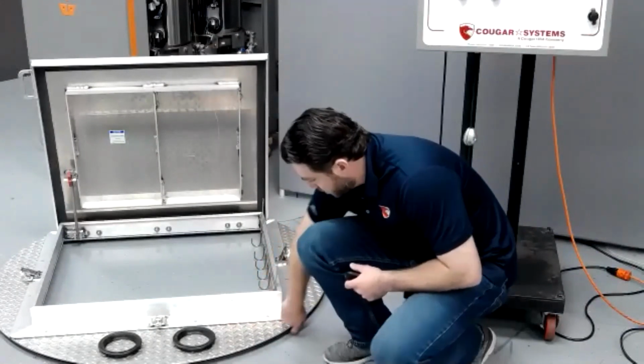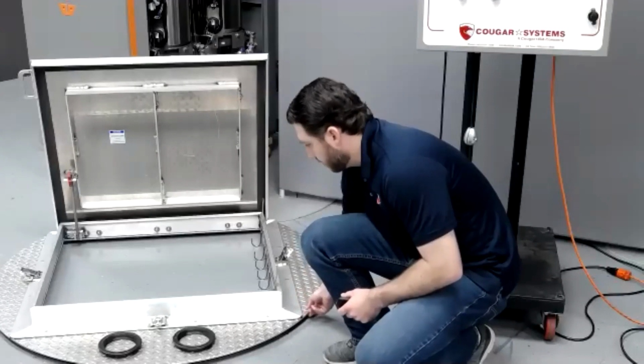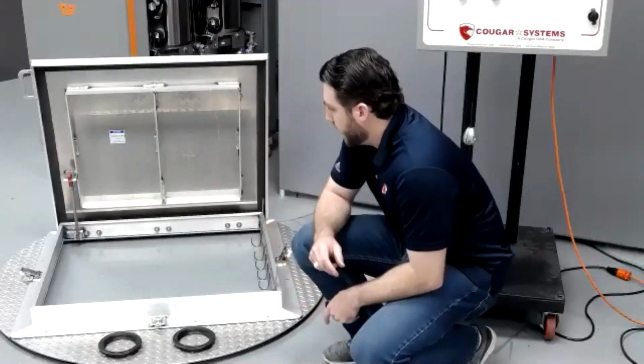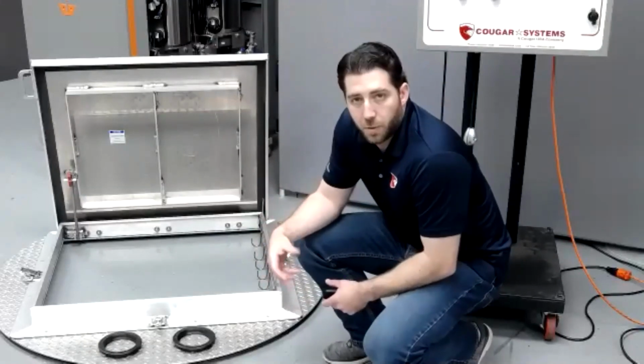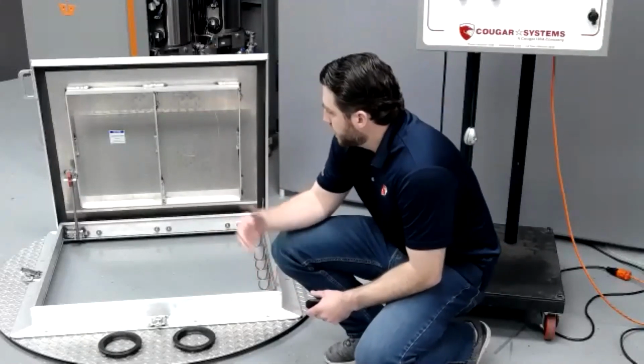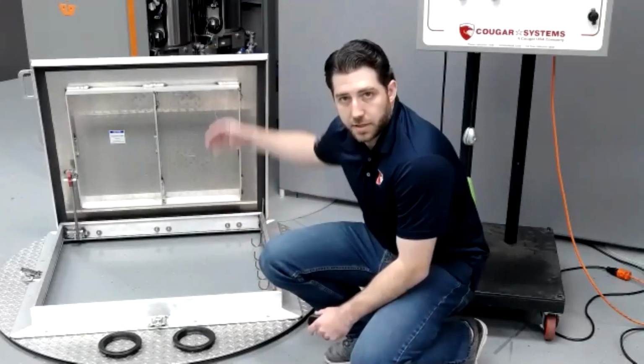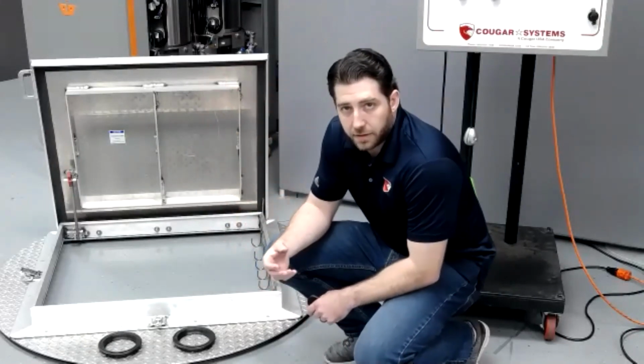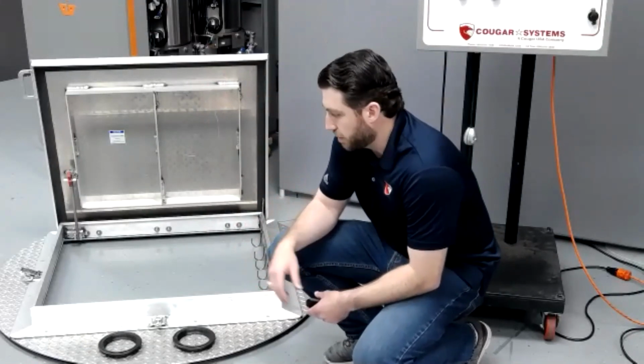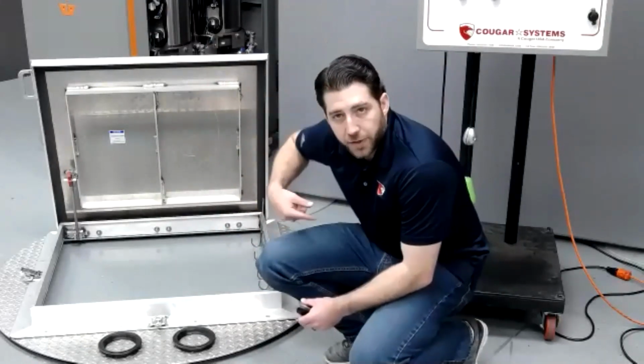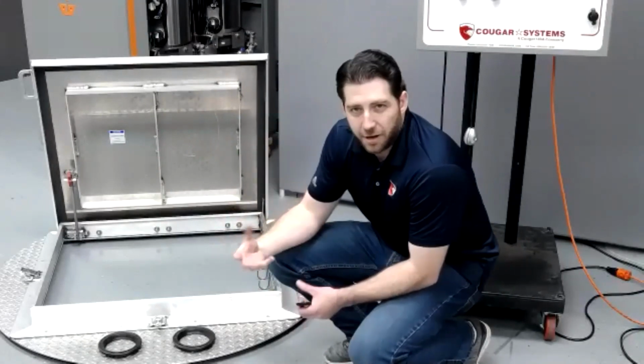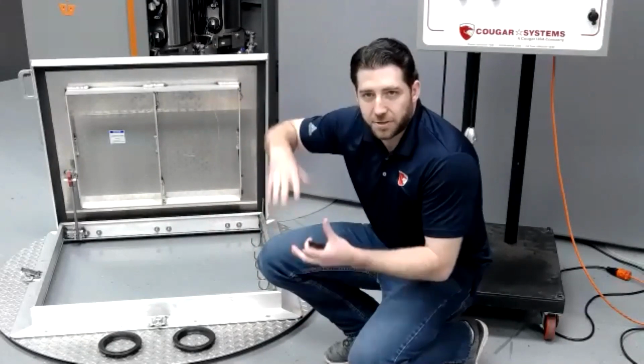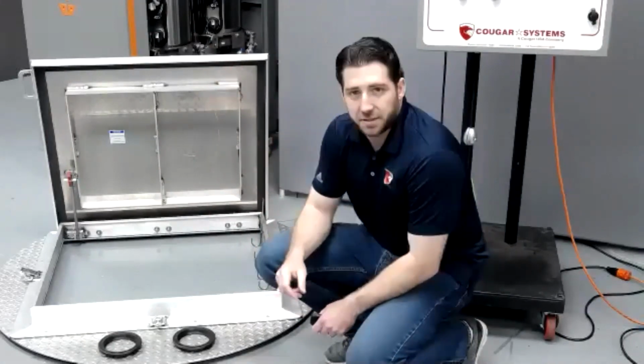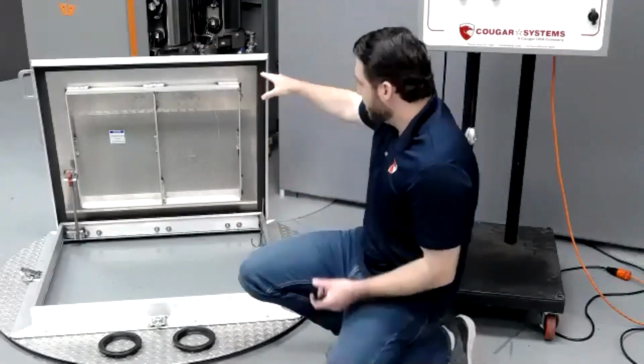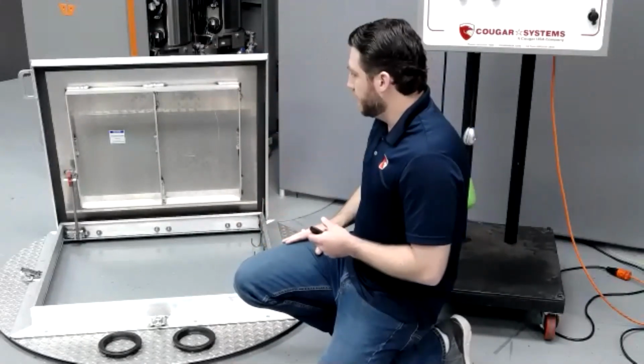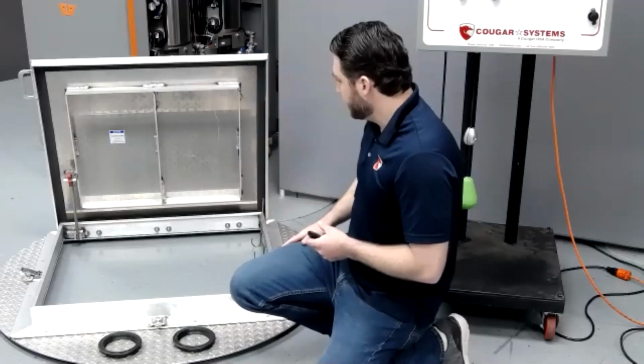And then the contractor would seal it here using caulking or other sealant to really seal in the gases. In terms of options for gas tight or watertight covers, this is a great one because you can open and close this hatch very easily without destroying the gasket material or ruining your seal. Some of the other options out there are bolted all the way around. You have the gasket all the way around, and once you take it off once, it's kind of like those old Broncos. If you ever took the cover off one of those, you put it back, and it never really sealed perfectly again. So you're going to be able to open and close this pretty easily and not have issues damaging that gasket material.